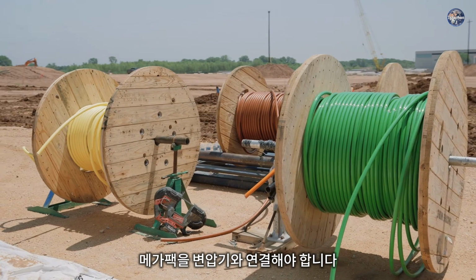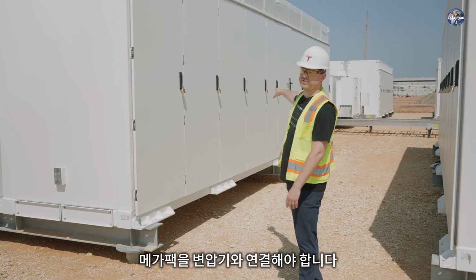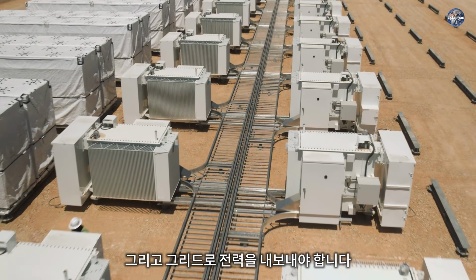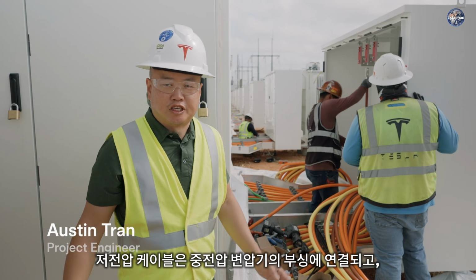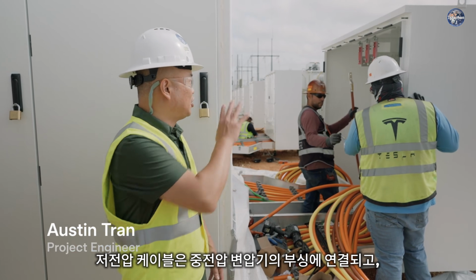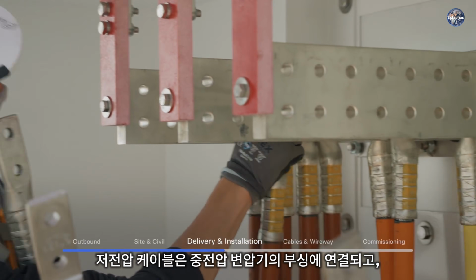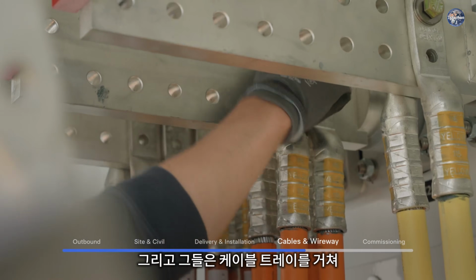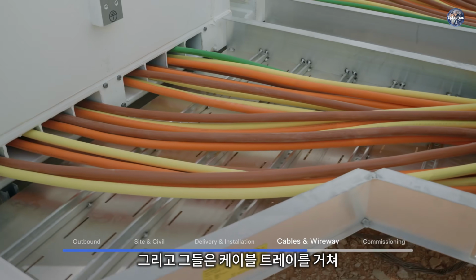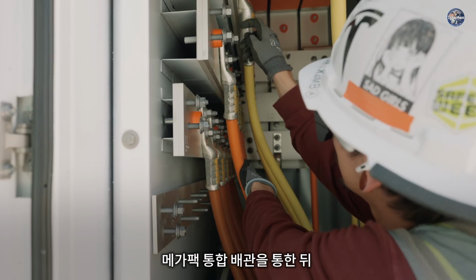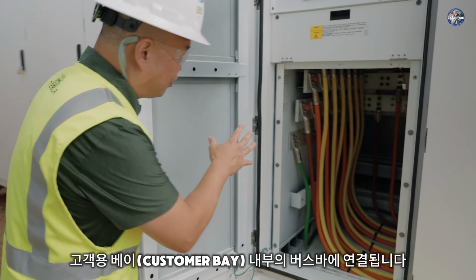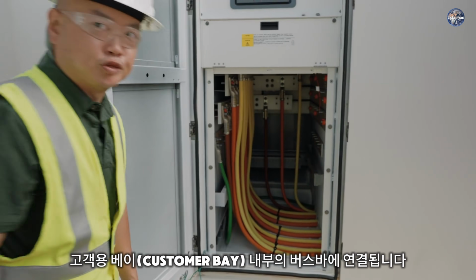Once a Megapack is installed on its foundation, the next step is to work with low voltage cables. Basically, we have to get the Megapack connected to a transformer that will get it out to the grid. The low voltage cables get installed on the bushings on our medium voltage transformer, and then they get routed through the cable trays and through the Megapack integrated raceway, and they get landed on the bus bars inside the customer bay.